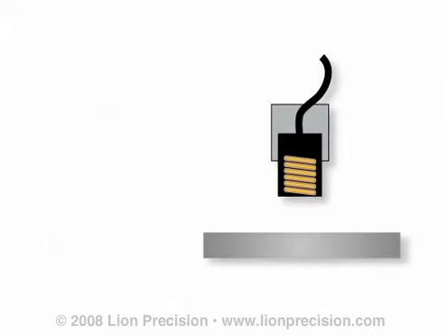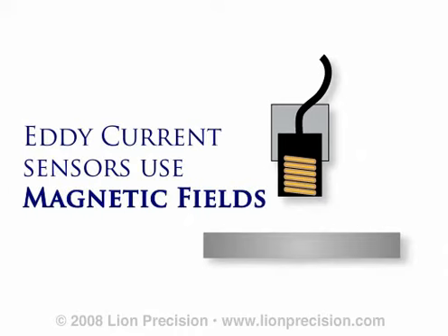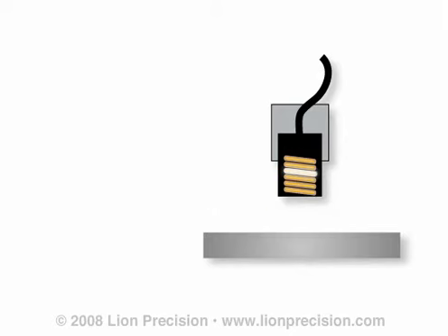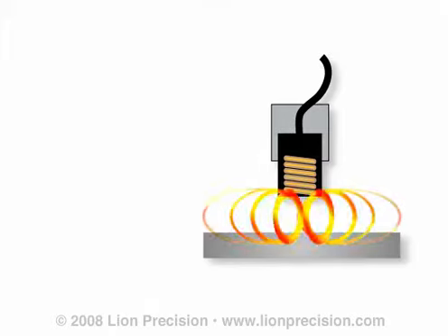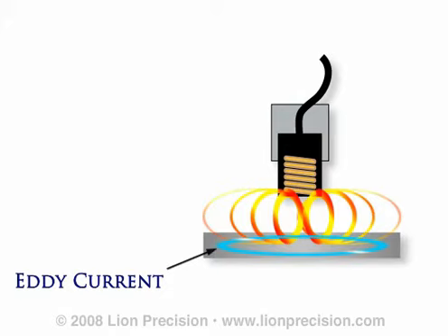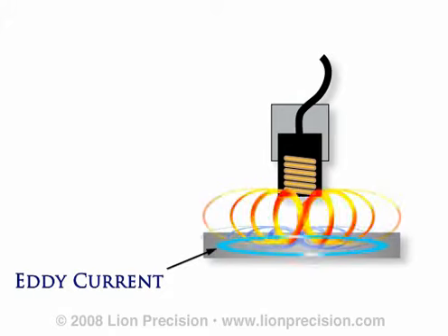Rather than electric fields, eddy current sensors use magnetic fields to sense the distance to the target. Sensing begins by passing alternating current through the sensing coil. This creates an alternating magnetic field around the coil. When this alternating magnetic field interacts with the conductive target, it induces a current in the target material called an eddy current. This eddy current produces its own magnetic field, which opposes the sensing coil's field.